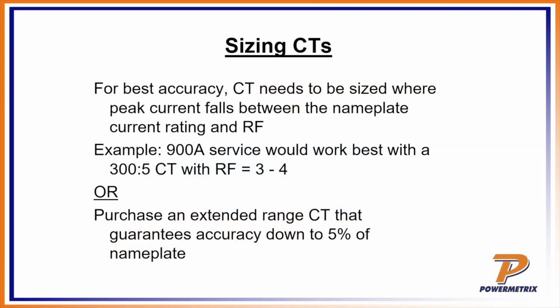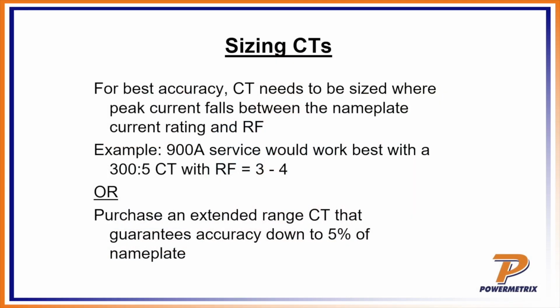Okay? So let's look at an example right here. I got a 900 amp service. Remember the one from earlier? So I got a 900 amp service, and it would work best with a 300 to 5 CT with a rating factor of 3 to 4. So think about that. If I got a rating factor of 3 on a 300 to 5, 3 times the 300 gets me to the 900, and I'm still getting that 0.3% accuracy. So absolutely you would want to go with the 300 to 5 with that rating factor.